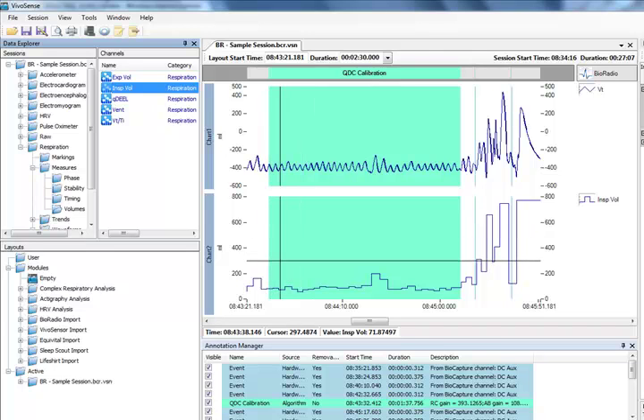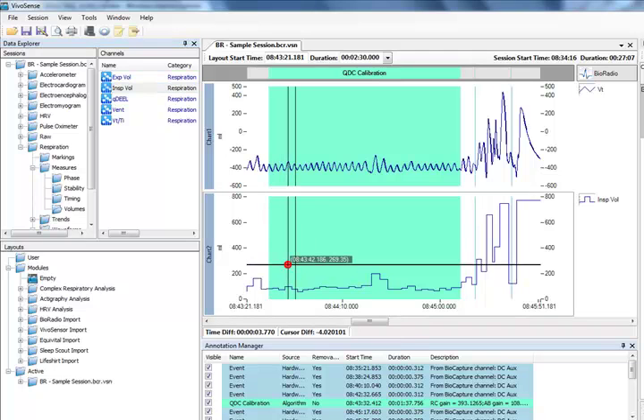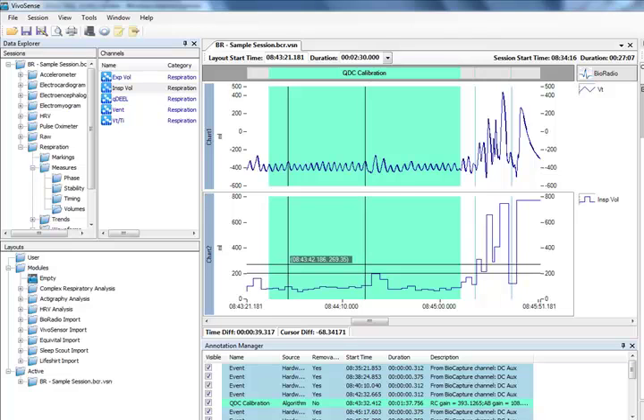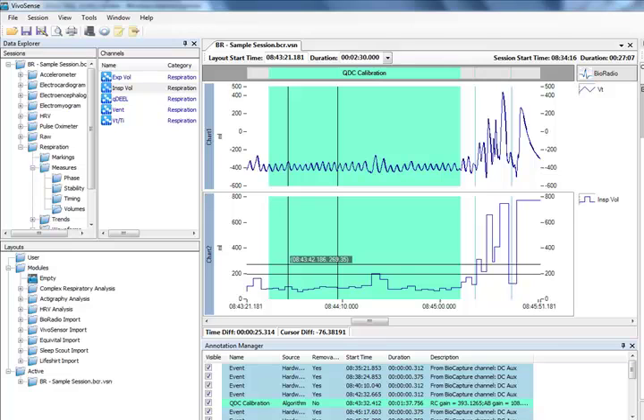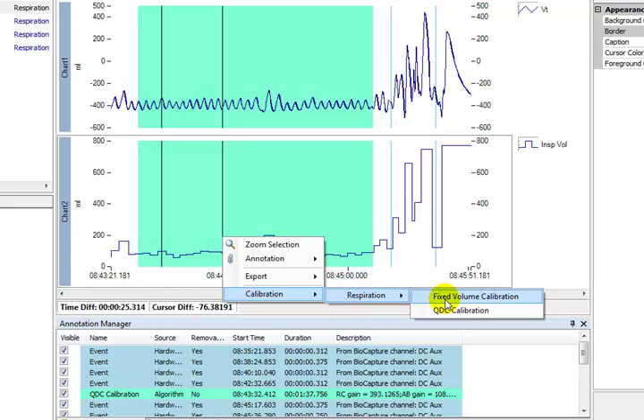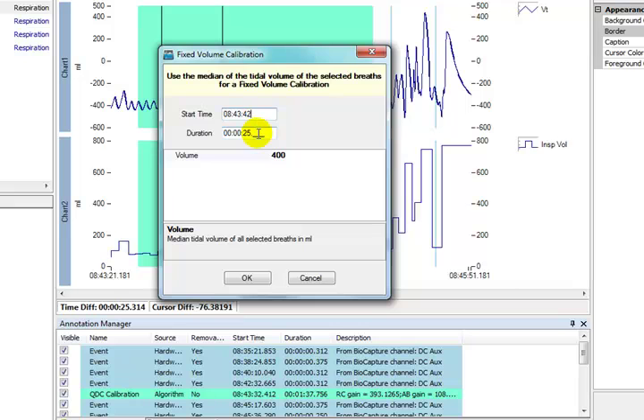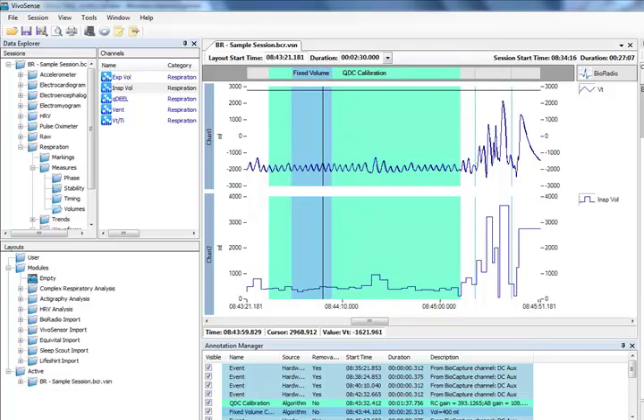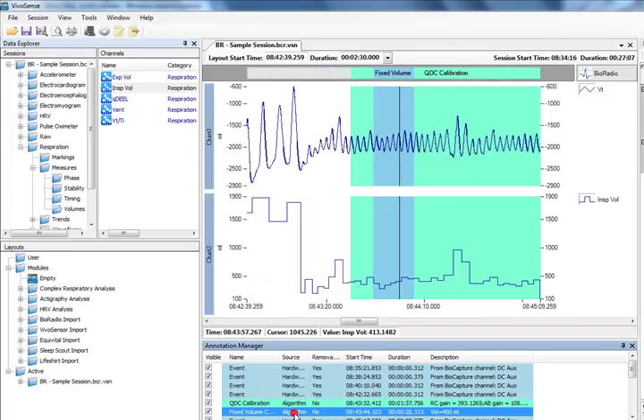On this channel, using the left mouse button, we drag the range over which the fixed volume was measured. The default volume is 400 mL. However, if our external fixed volume calibration measured more or less than 400 mL, this may be edited in the fixed volume calibration dialog. We may also change the start time and duration for the calibration range here. Press OK and a fixed volume calibration is performed over the selected range. An annotation is added to the Annotation Manager to identify the range of our calibration.